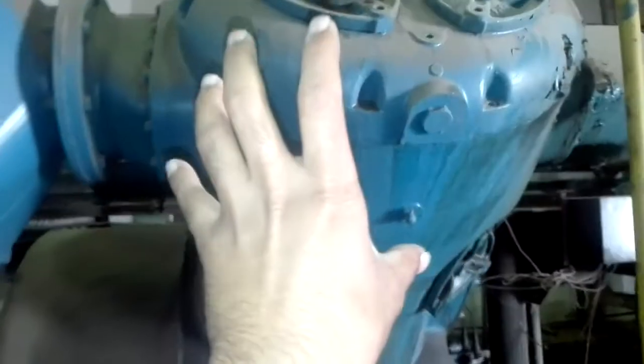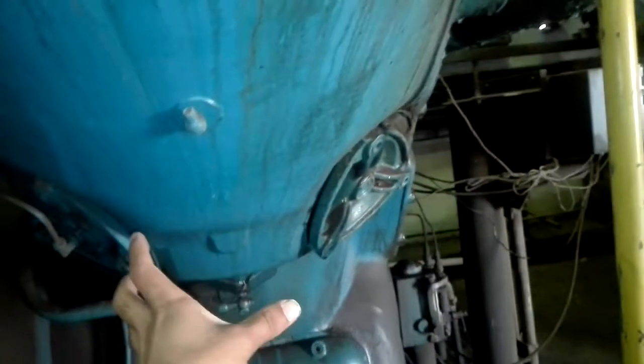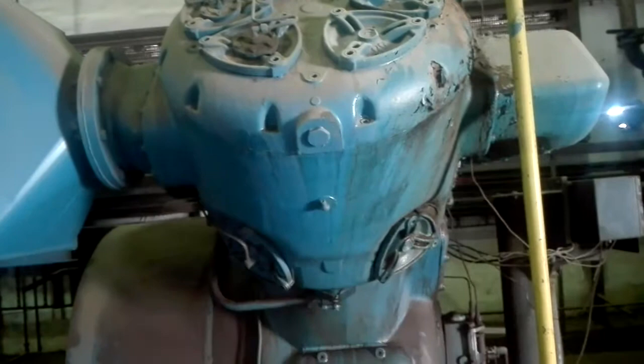The air coming from the filter goes to this piston which is inside here. This is the piston cylinder — the first stage of the compressor. The first stage has a larger volume. The delivery side of the first stage goes around there and then goes to the suction of the second stage, which is here.